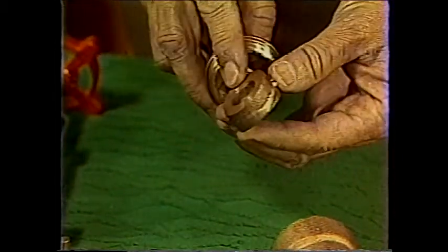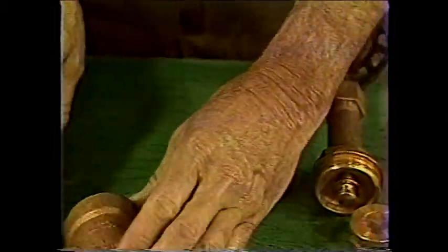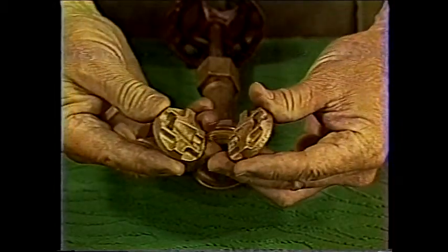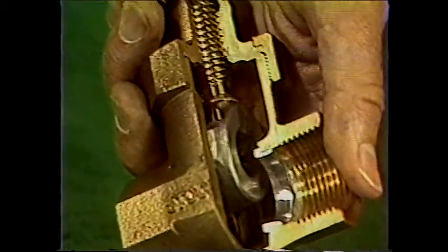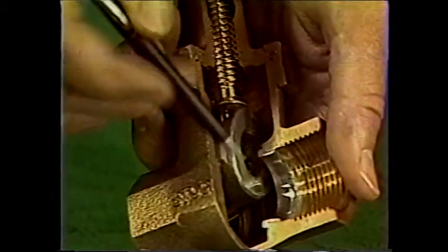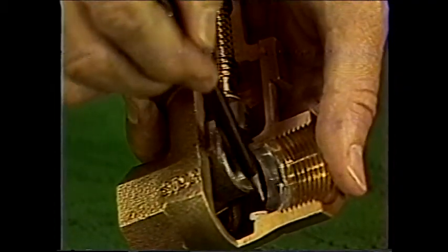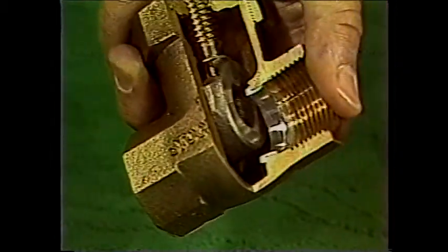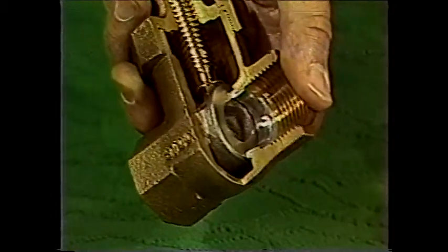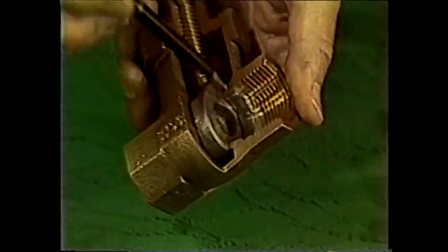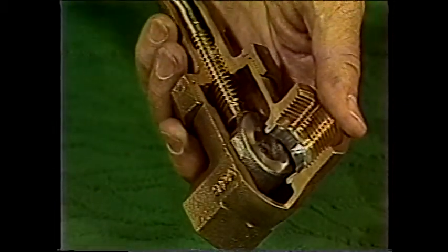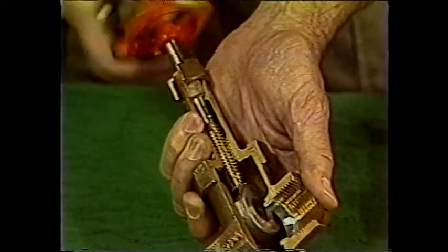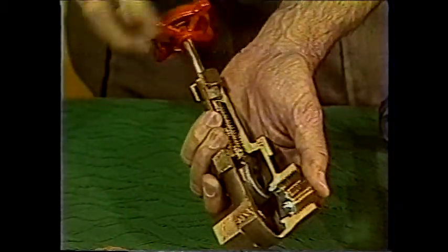The gate or wedge may be one piece, like this, which is known as a solid or a single wedge, or it may be in 2 interlocking halves, in which case it is called a split or double wedge. The closure is accomplished by metal-to-metal contact between the surface here on the gate, or disc, and the surface here on the seats, both of which have been ground to give a smooth finish. These mating surfaces may or may not be hardened, depending upon the service for which they are intended. Gate valves are furnished with rising stems like this, where the stem rises up out of the valve and brings the gate with it as it comes.